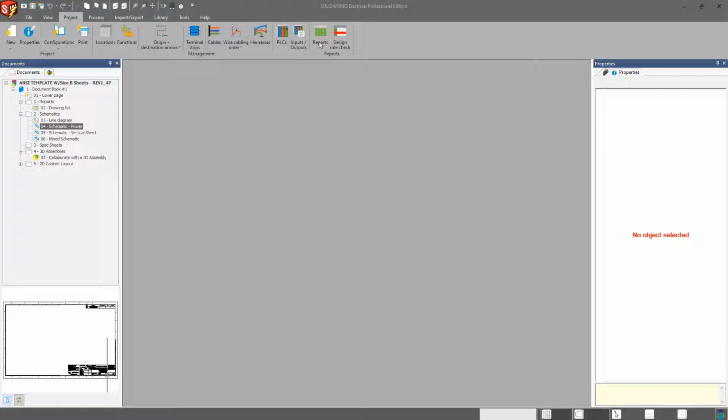Your design rule checks will look at specific information in your schematic and create a report to give you information such as maybe there's too many pins, too many wires going into one pin, or maybe you have used a 16 gauge wire and put that onto a connection point that requires you to have a 24 gauge. So it's going to give you certain information like that. Fill duct ratio is another one.